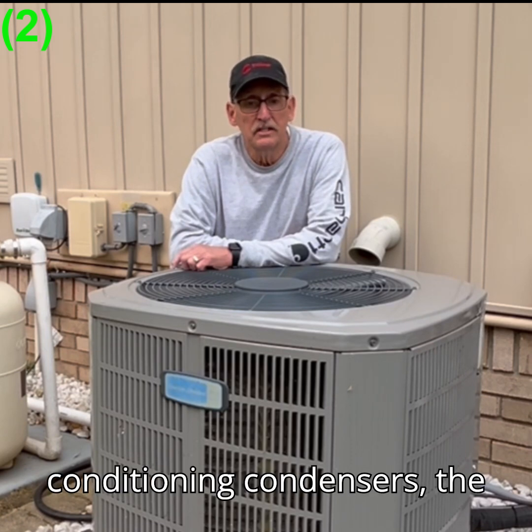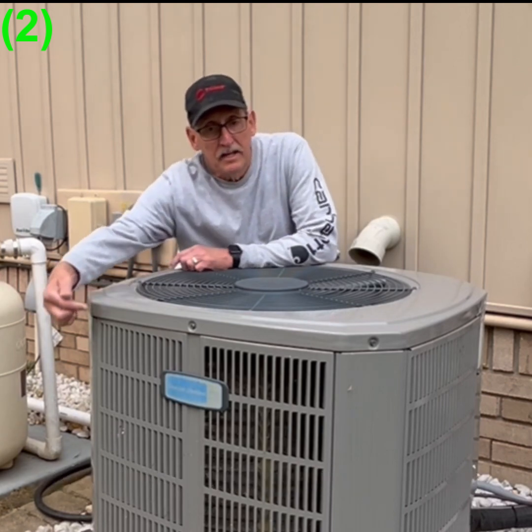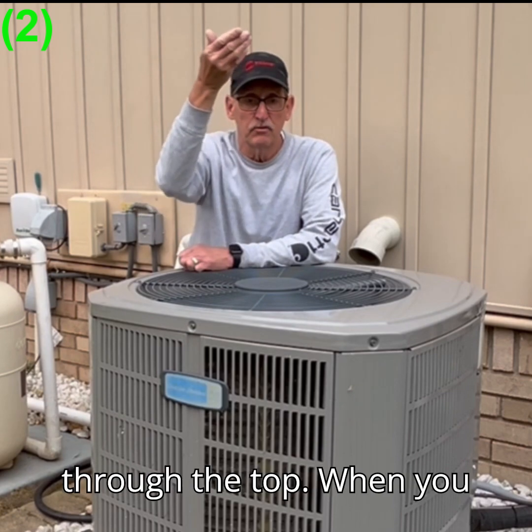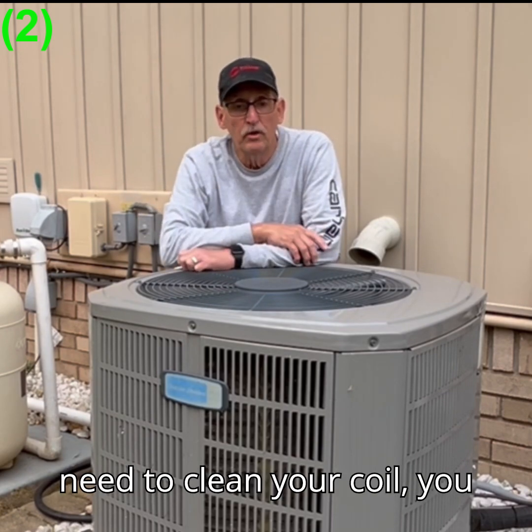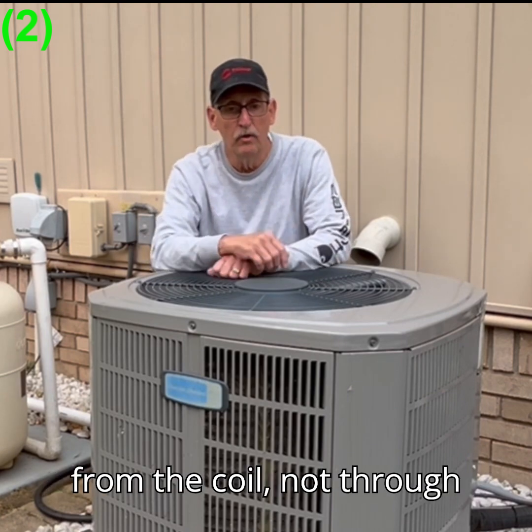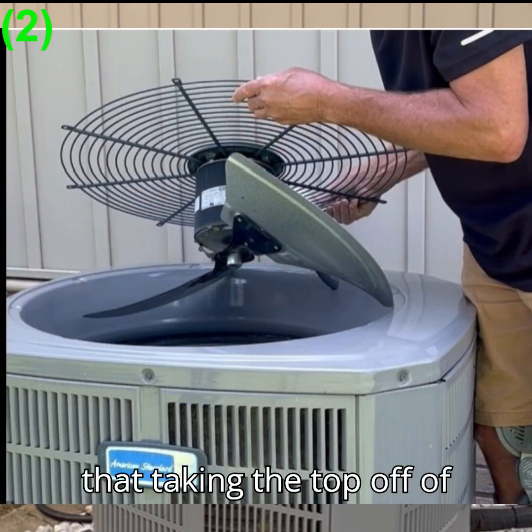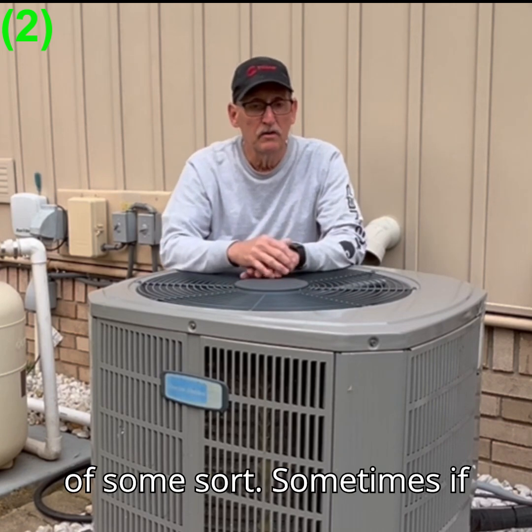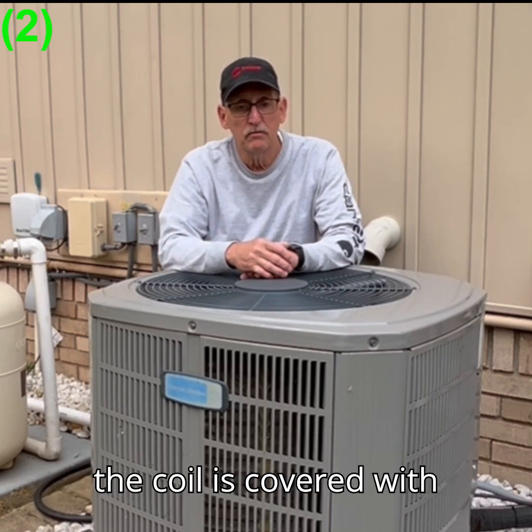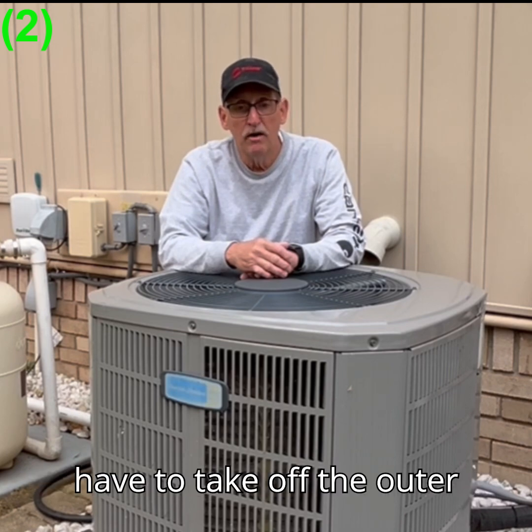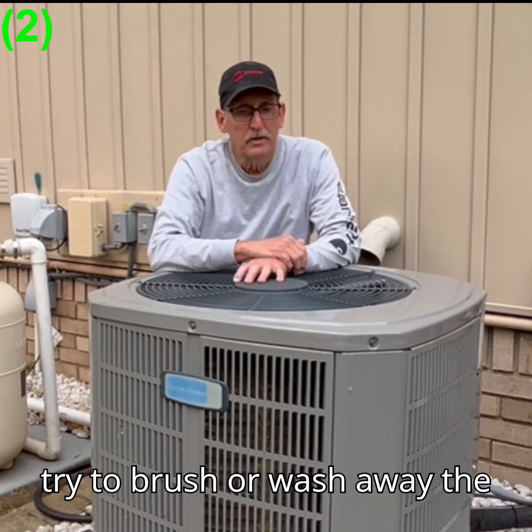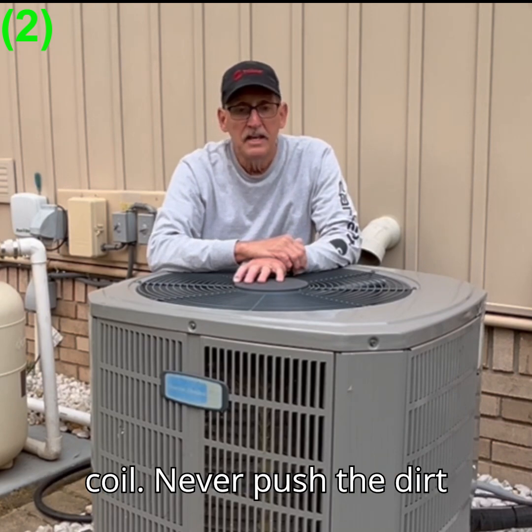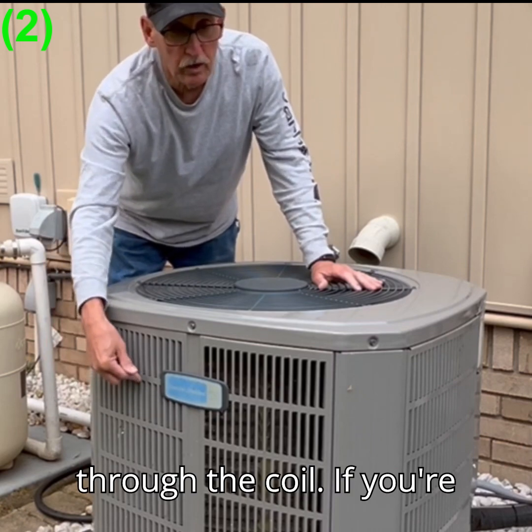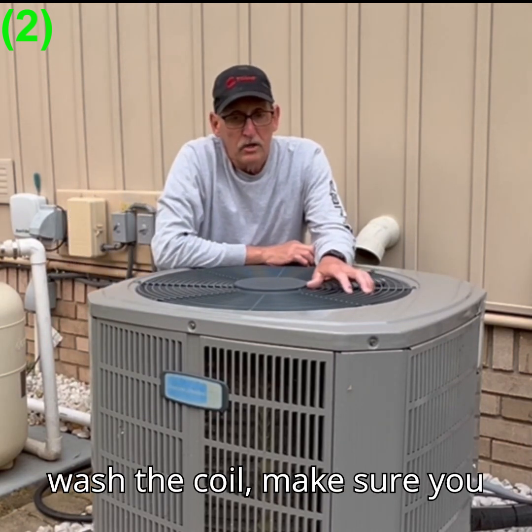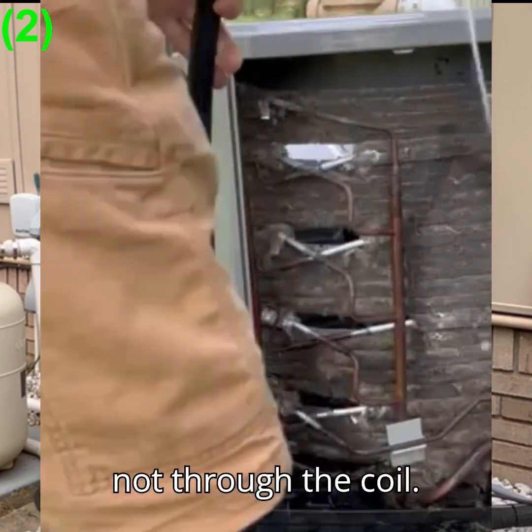In most air conditioning condensers, the air is being sucked from the outside and then exits through the top. When you need to clean your coil, you need to push the debris away from the coil, not through the coil. That usually means taking the top off of the fan and blowing air through the coil with an air hose of some sort. Sometimes if the coil is covered with debris or cottonwood, you may have to take off the outer screen of the condenser and try to brush or wash away the dirt and debris from the coil. Never push the dirt through the coil. If you're using some type of hose to wash the coil, make sure you wash it down over the coil, not through the coil.